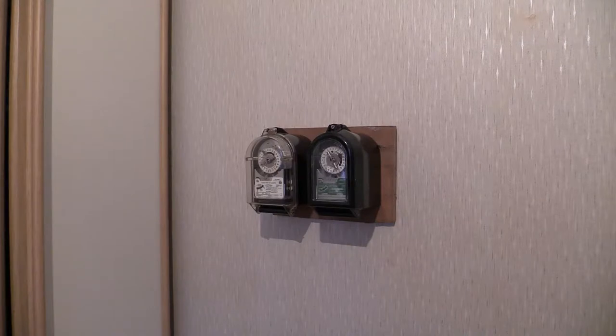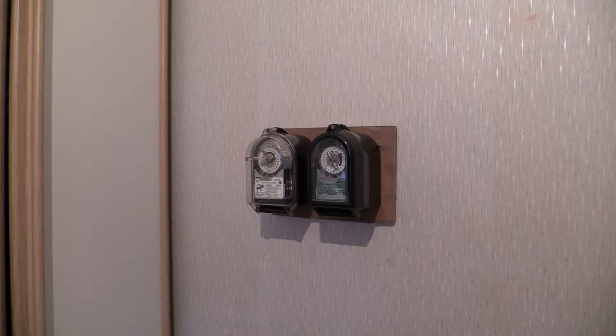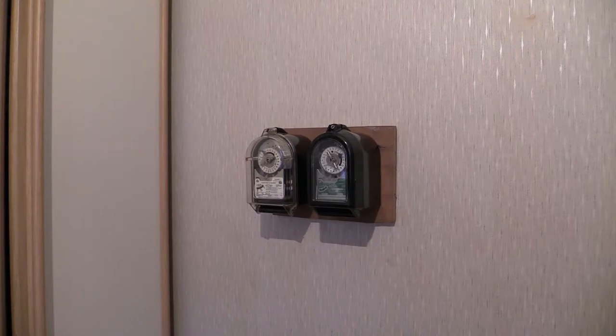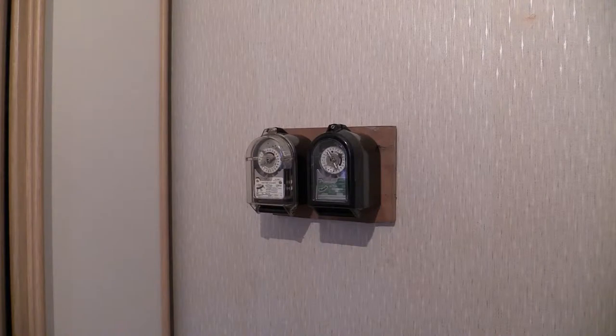With these time switches, because they are mechanical, they do have a spring reserve mechanism in them. The spring reserve is good for 15 days of power loss, and the spring reserve can be wound up with the little square shank in the middle of the clock faces. We shall be zooming in now and taking a look at these time switches.